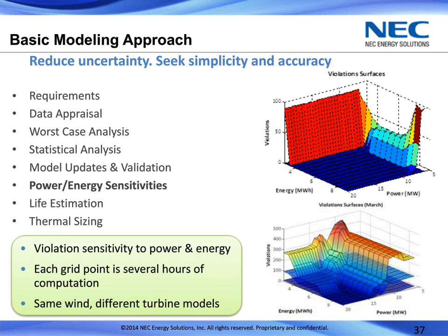So skipping through a few steps here and jumping into some of the outputs, we can see a couple of different surface plots where we're looking at violations of these requirements for ramp rate based on different power and energy capabilities. Now each point in these grids is the result of an analysis of a year's worth of data, and the system performing its controls response to a specific control algorithm. So part of the process is obviously refining that control algorithm. We've sort of stepped over that part of the process.